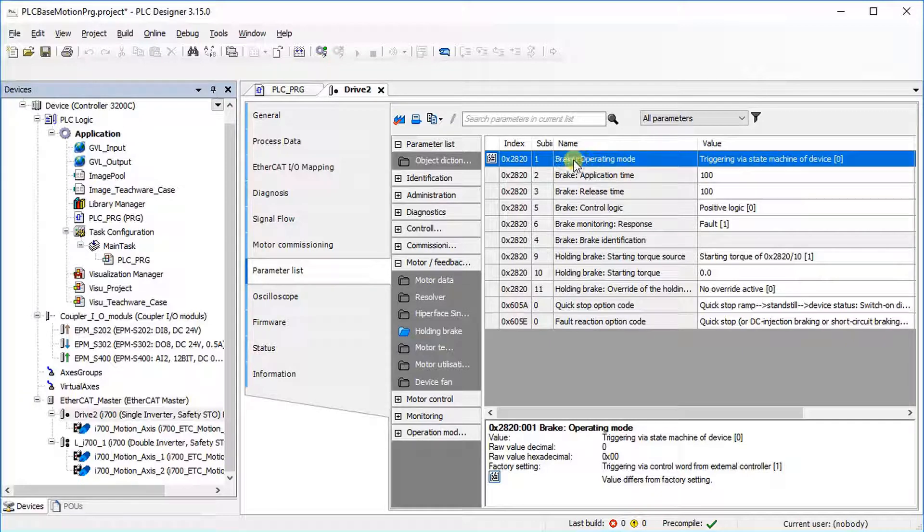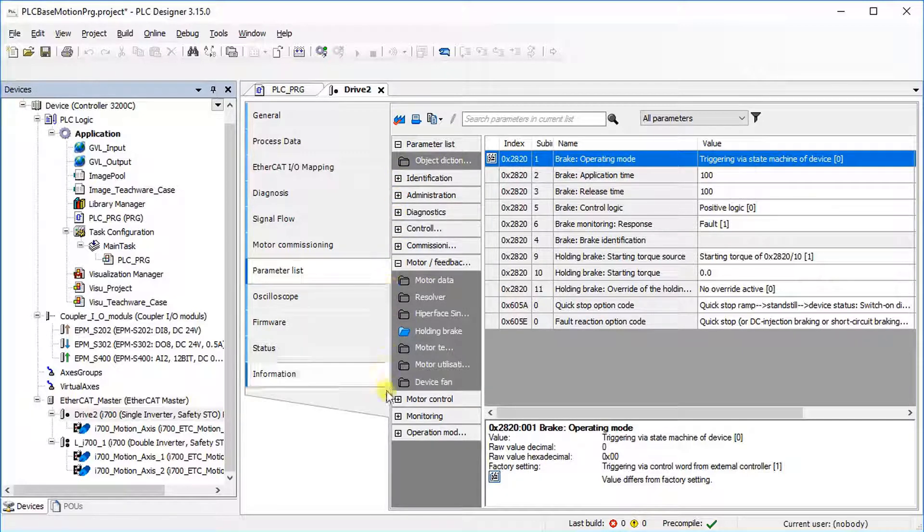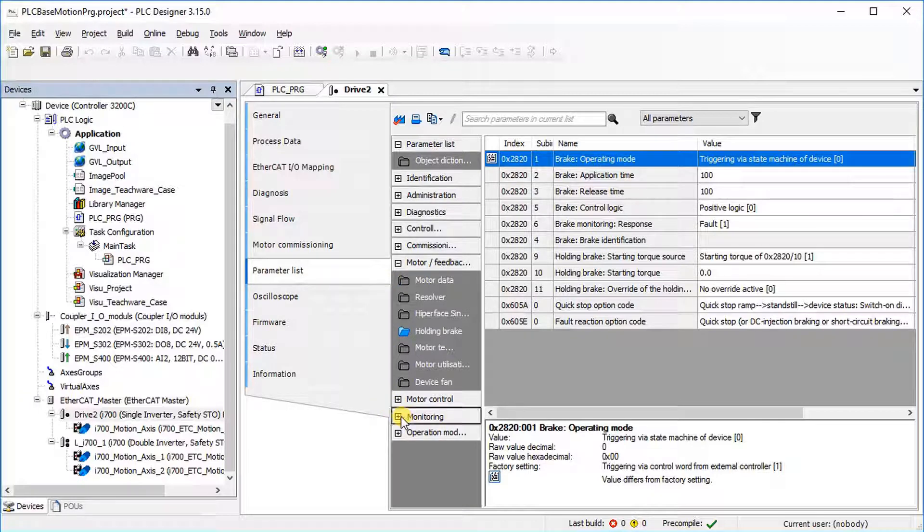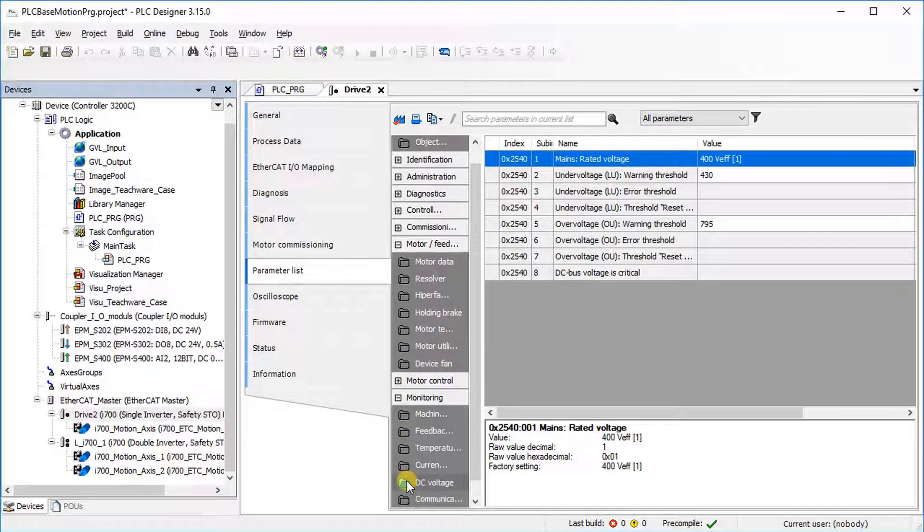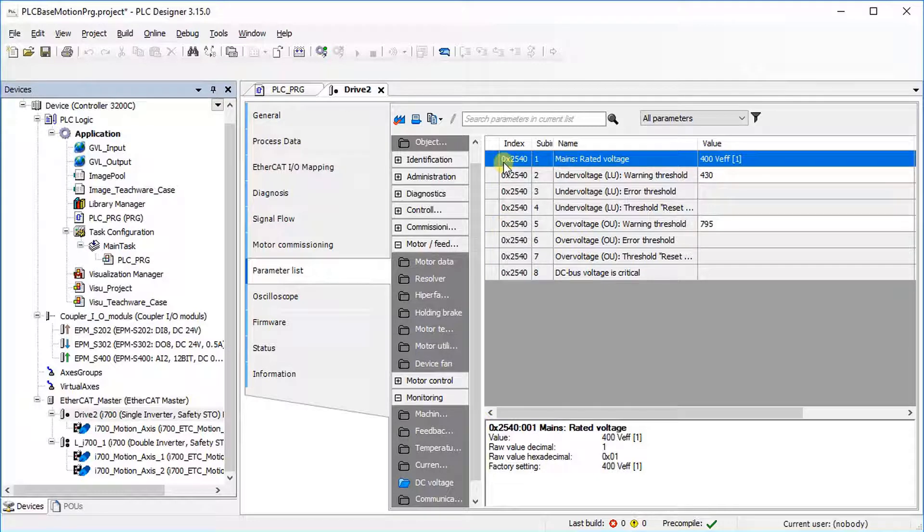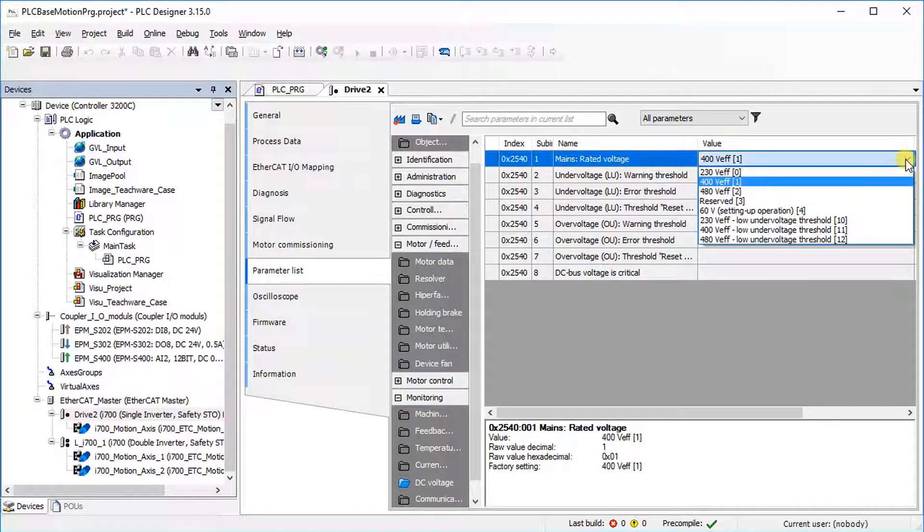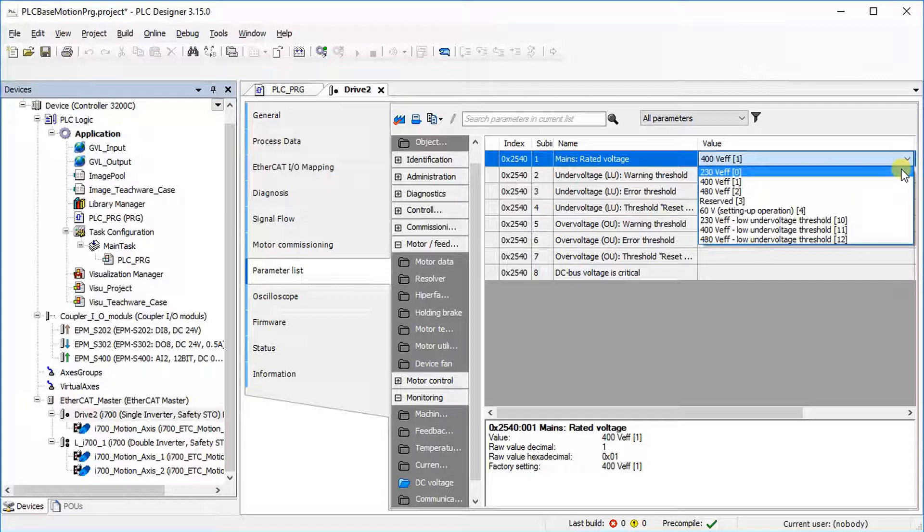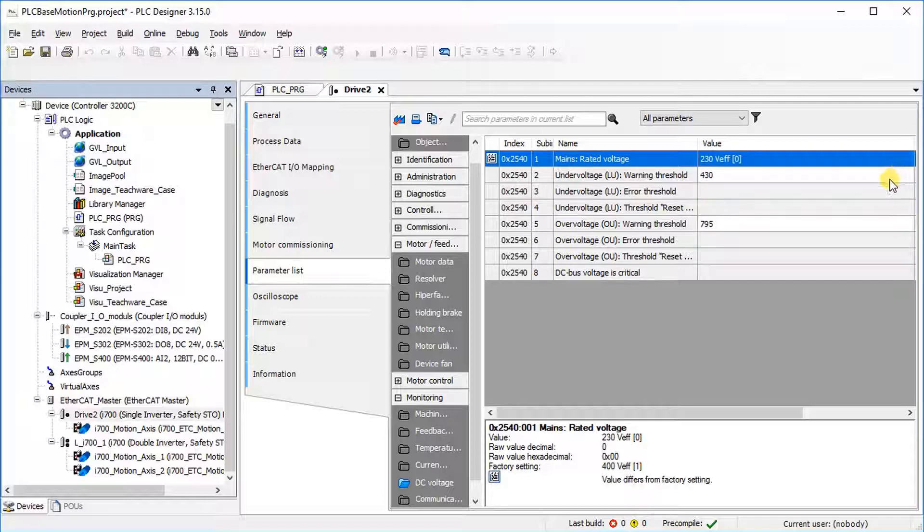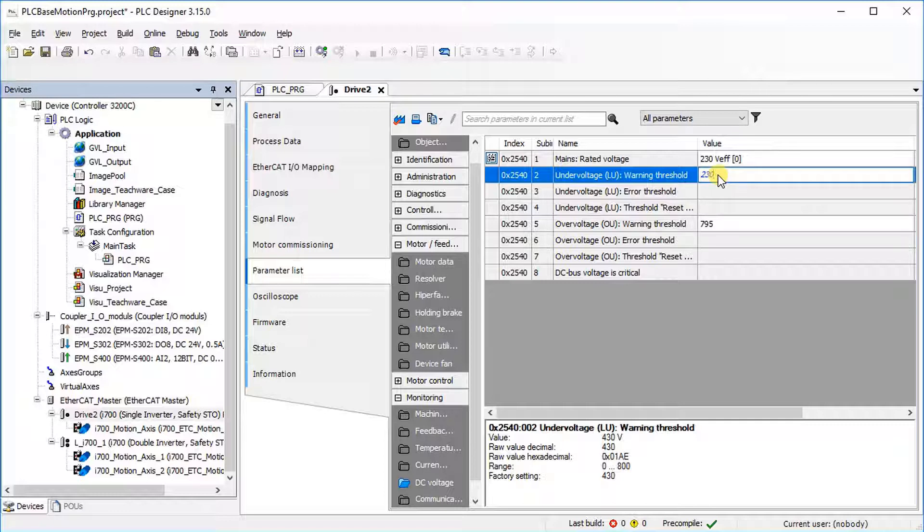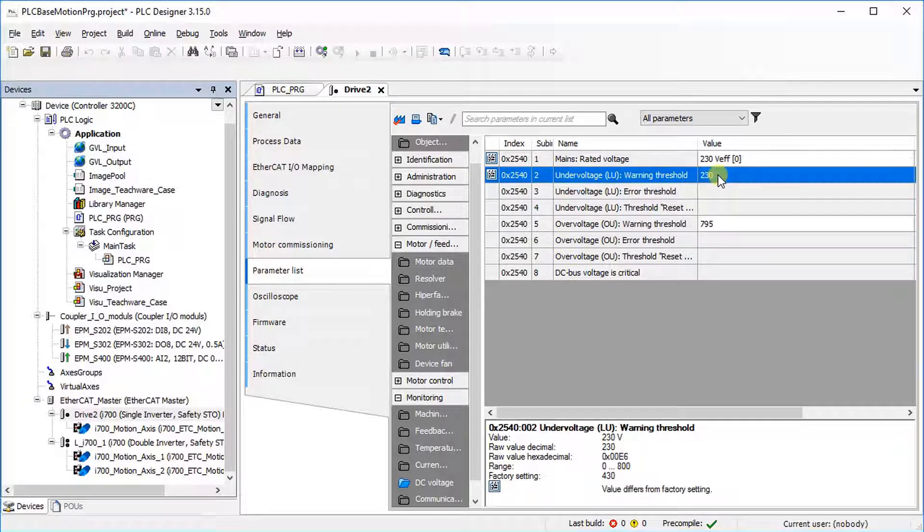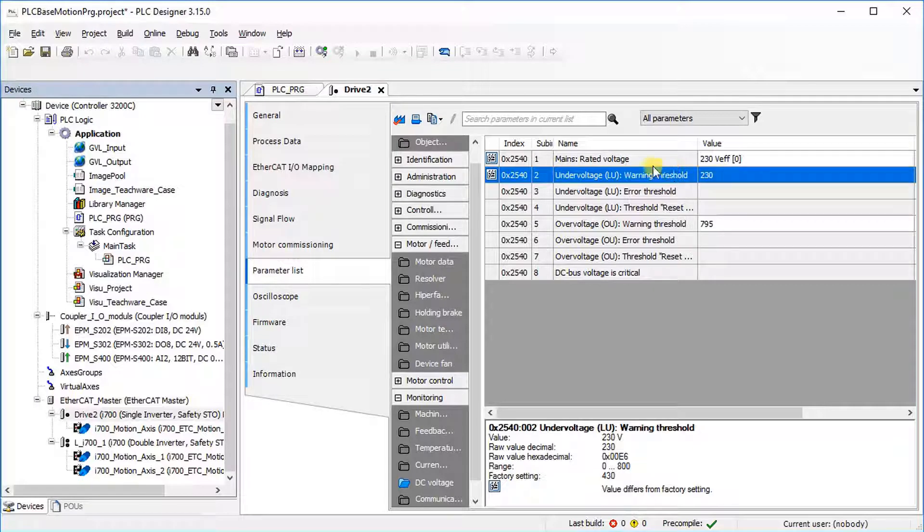Go to DC Voltage under the Monitoring tab. As the i700 teachware case has a 230V single phase supply, set the mains voltage to 230V. Set the undervoltage warning threshold to 230V as well. It may change according to the input supply voltage. Press the save button and close the tab.